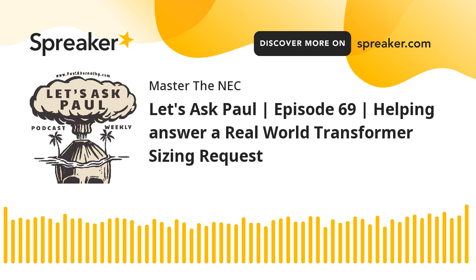So here's what it says for 240.21(C)(4). For those following along, pause this podcast, grab your code book, and blow the dust off of it. It says, outside secondary conductors: where the conductors are located outside of a building or structure, except at the point where they terminate, or the load terminates, which yours sounds like everything's outside, so it doesn't matter, and it complies with all of the following. Okay, so you have four conditions here. Number 1, the conductors are protected from physical damage in an approved manner. Again, approved manner being whatever the AHJ is okay with.